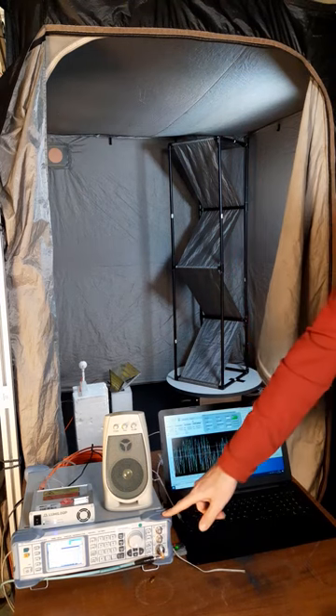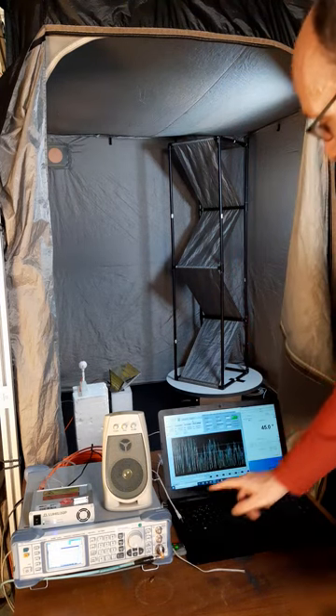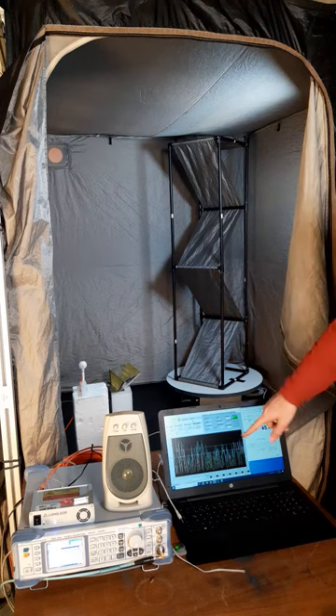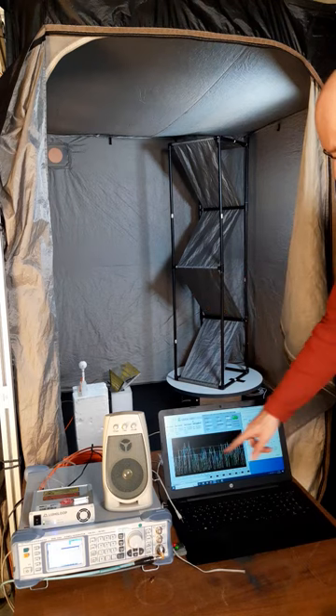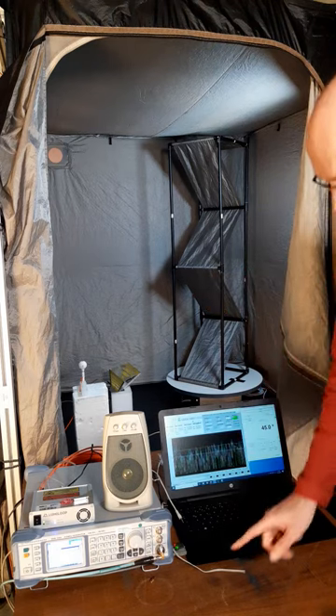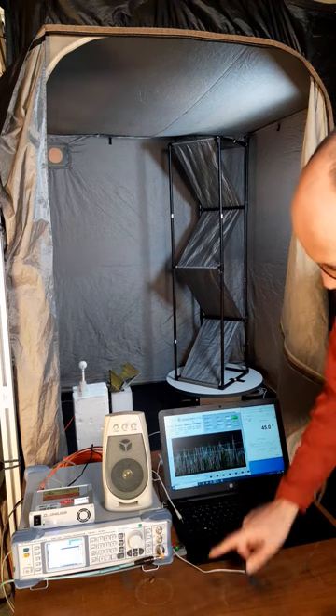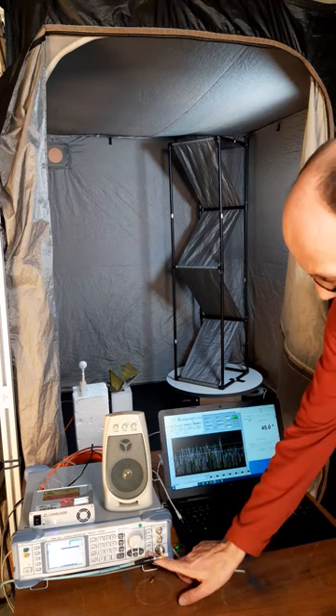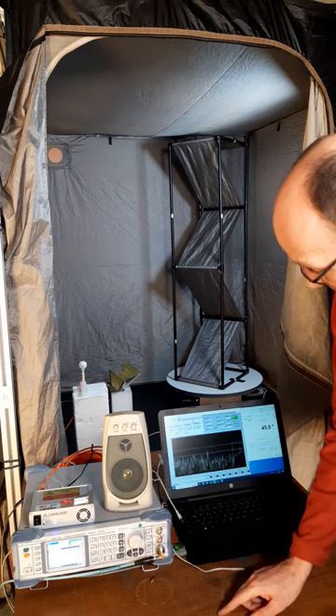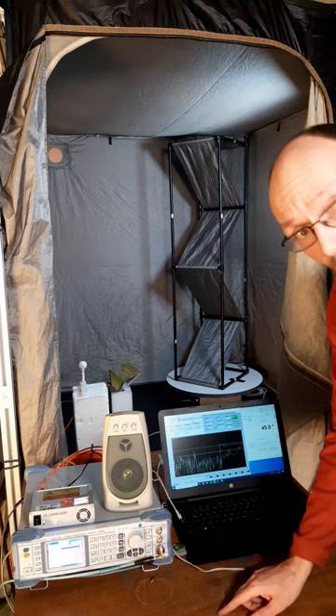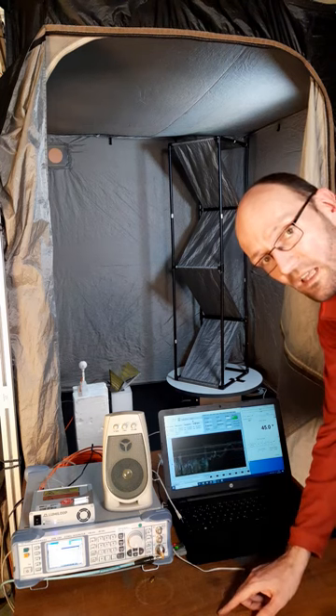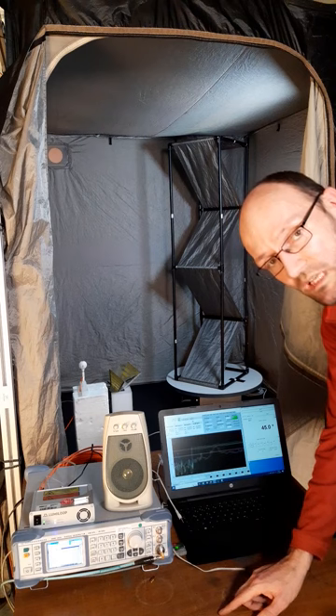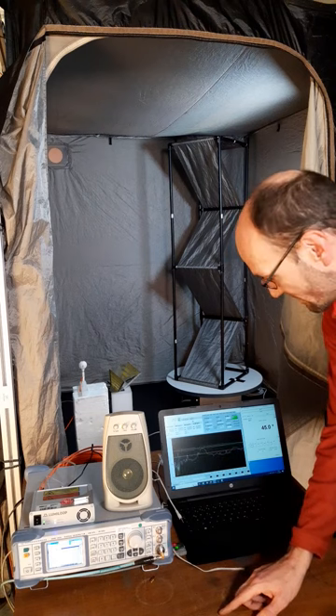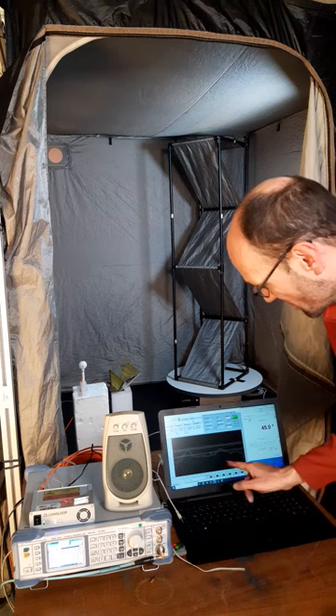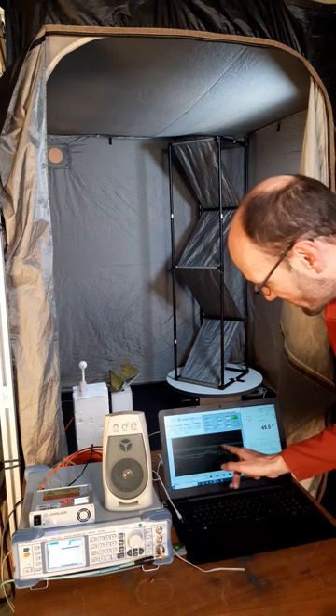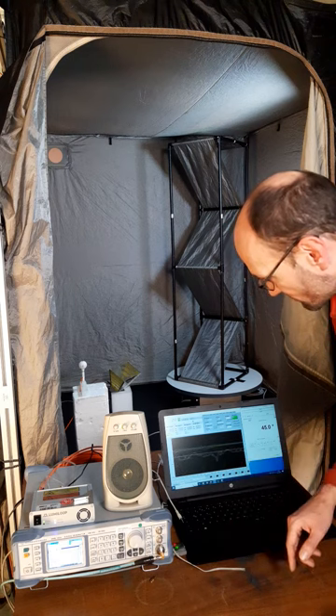I have a signal generator here and a field probe that measures the field, and here you can see the field probe measurements over time. At the moment it's just noise. If I enable the signal generator, frequency is 1 gigahertz and the power level is 20 dBm, corresponding to 100 milliwatts, then we get a nice and almost stable field here.